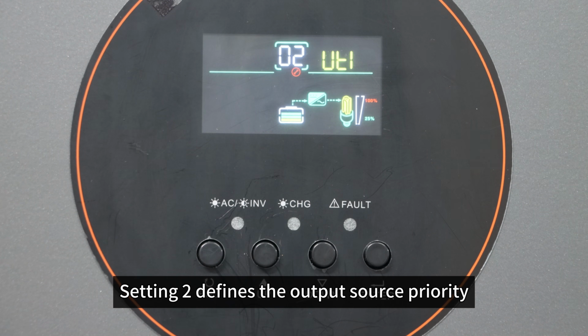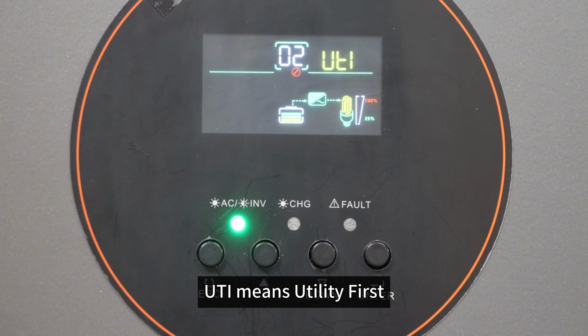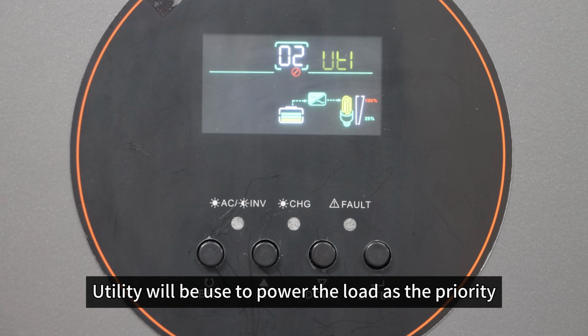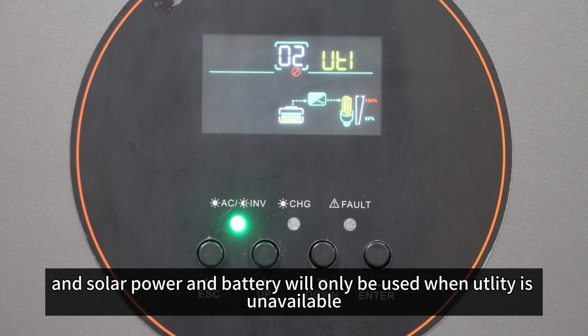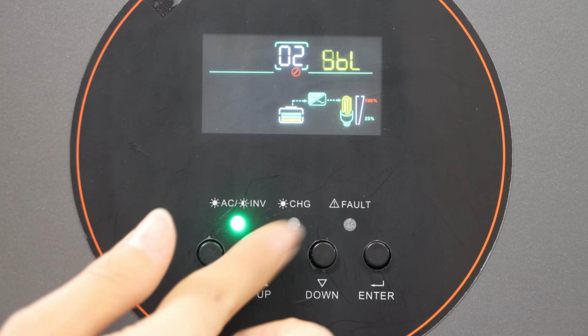Setting 2 defines the output source priority. UTI means utility first. Utility will be used to power the loads as the priority, and the solar power and battery will only be used when utility is unavailable.